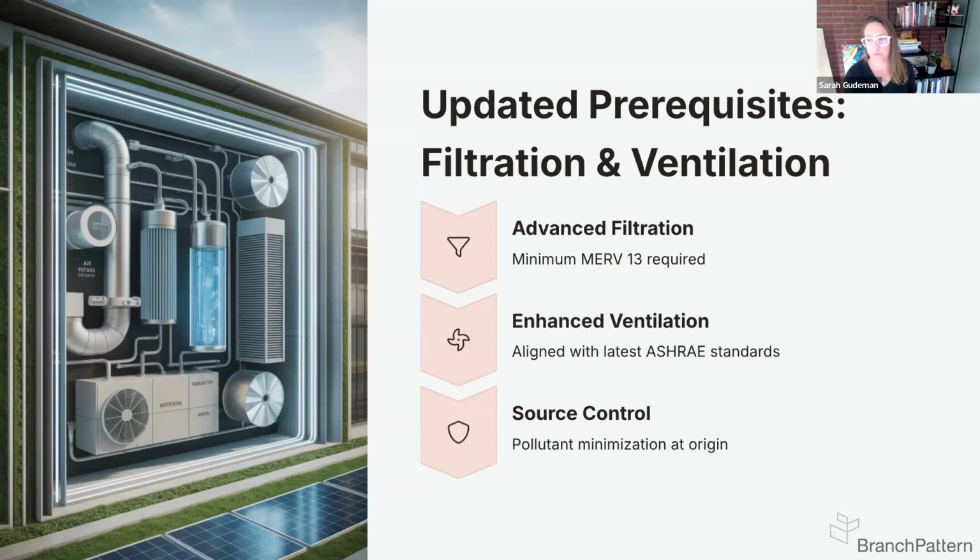there's also a requirement for outdoor air monitoring and measurement, which you may be familiar with from previous versions of LEED. And that is only for systems that have outdoor air intake greater than 1,000 CFM. So there are, again, some nuances for buildings like healthcare facilities or residential provisions in the rating system. And this prerequisite is also where the requirement for entryway systems now lives, if you're wondering where that went.